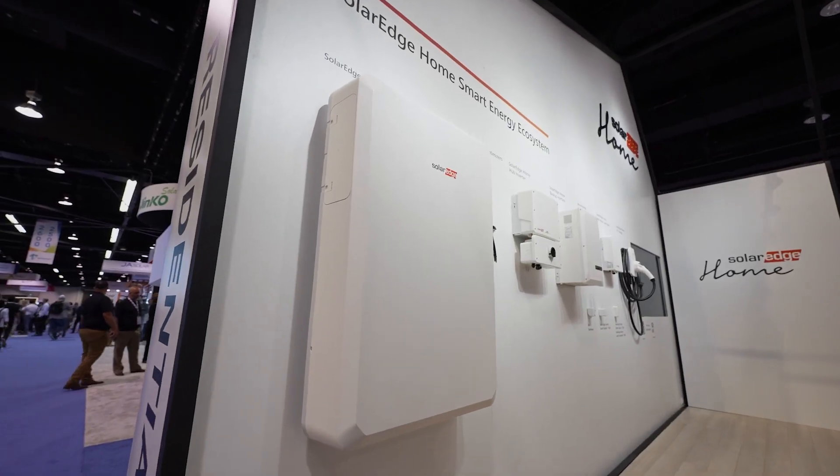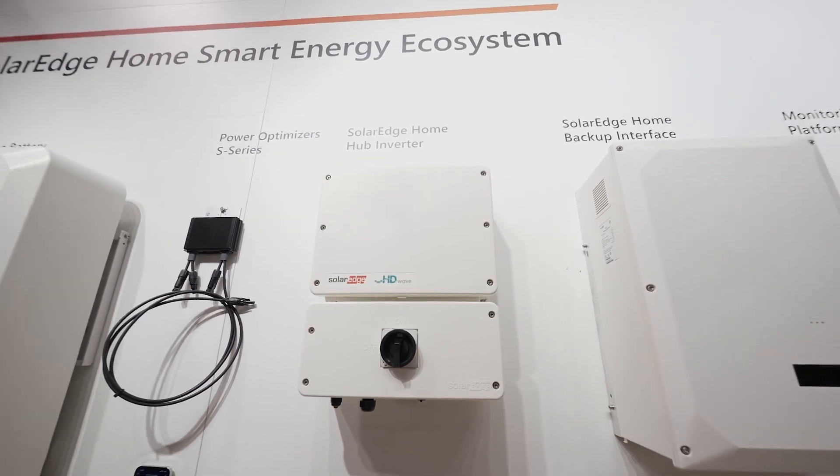SolarEdge has got you covered. Let's talk about mounting. Spacing and finding places to mount batteries is becoming more and more difficult. We have to maintain three feet away from doors, windows, and other batteries. But SolarEdge has got you covered — we have our UL9540A test report done, which allows us to have reduced spacing. We can maintain six inches away from batteries and doors and windows.